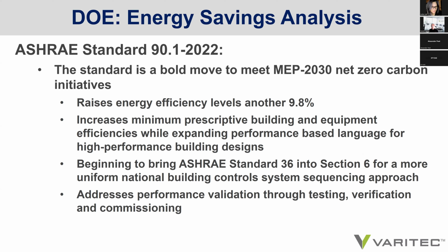The standard is a bold move to meet the MEP 2030 net zero carbon initiatives, and certainly in an attempt to achieve a 50% reduction of greenhouse gas emissions in comparison to the 2015 standard by 2030. It raises the energy efficiency levels by another 9.8% over 90.1 2019. It increases minimum prescriptive building and equipment efficiencies while expanding performance-based language for high-performance building designs.